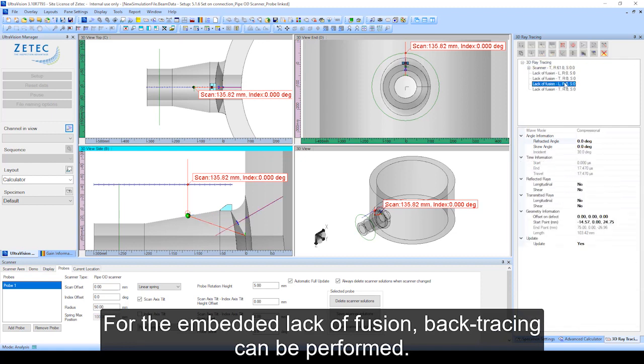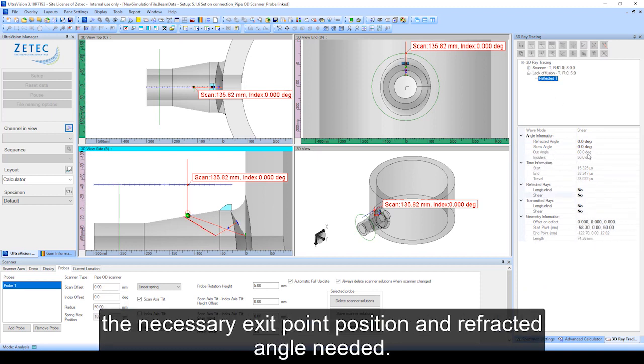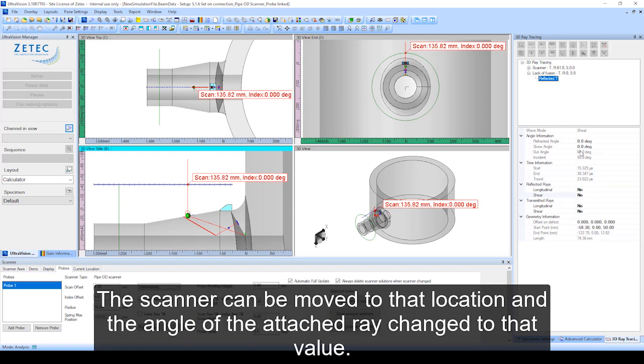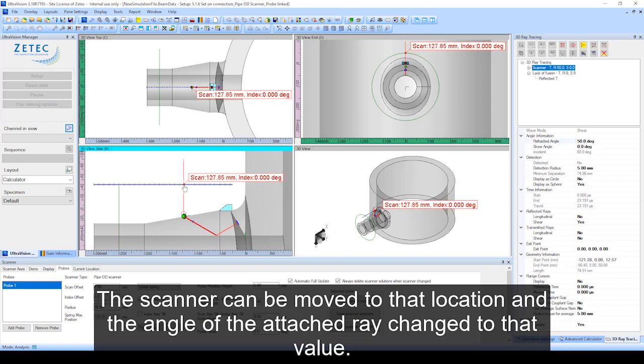Backtracing can be performed. The endpoint of the second part of the ray indicates the necessary exit point position and refracted angle needed. The scanner can be moved to that location and the angle of the attached ray changed to that value.